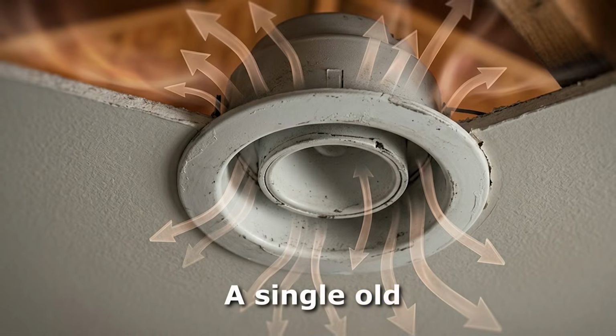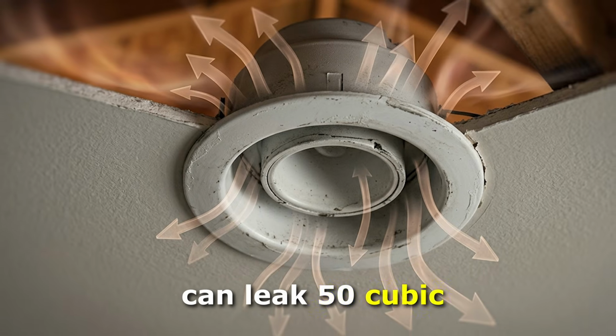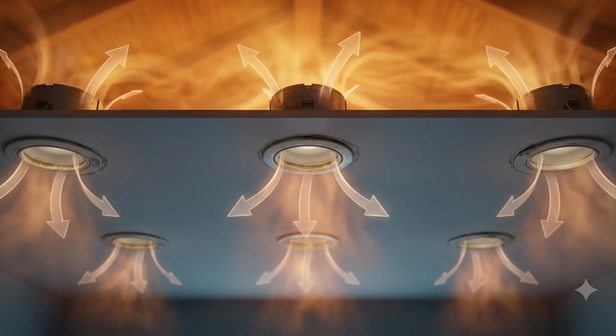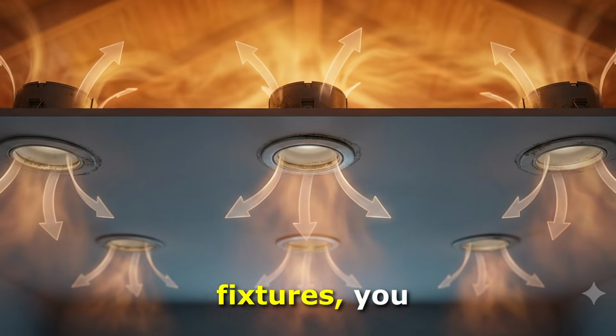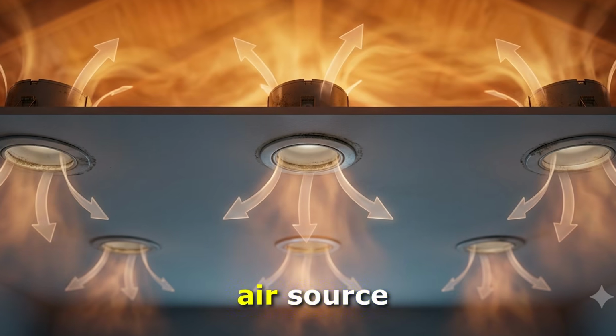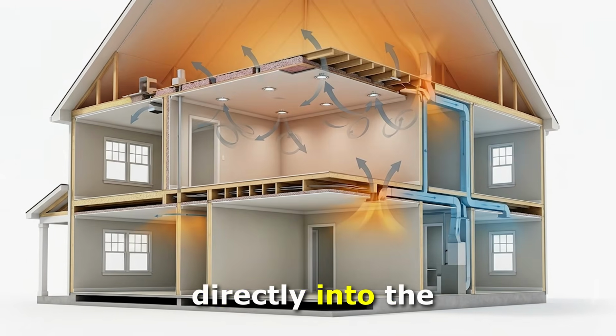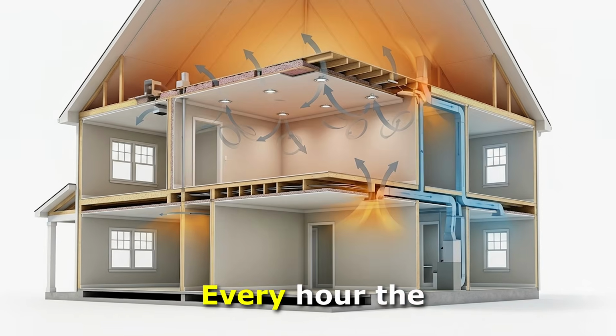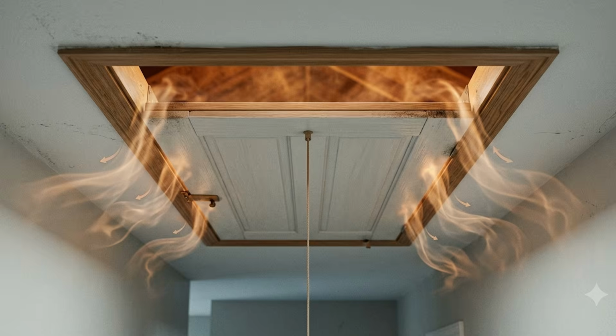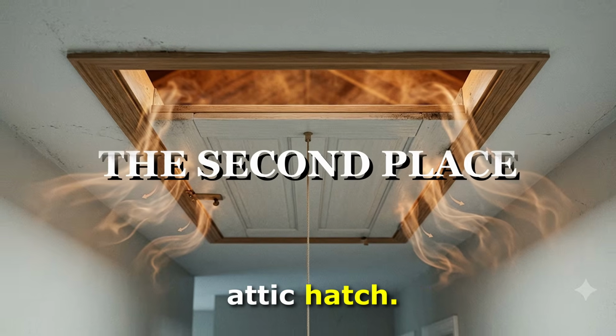A single old recessed light can leak 50 cubic feet of air per hour. If your hot room has 6 of those fixtures, you have a 140-degree air source pouring heat directly into the room continuously. Every hour the system runs. The second place is the attic hatch.